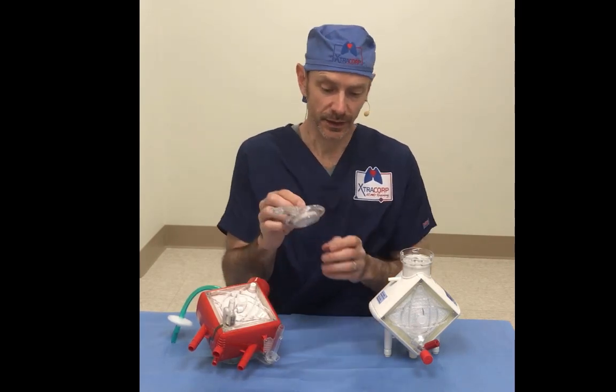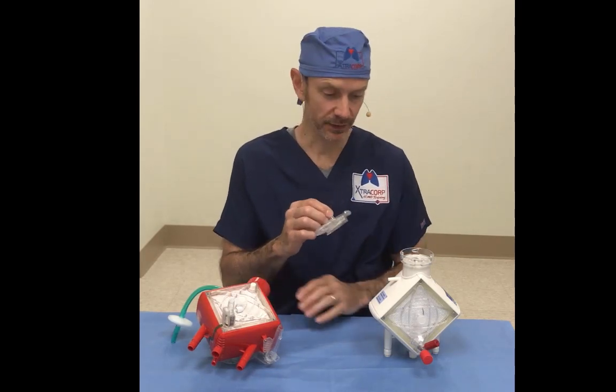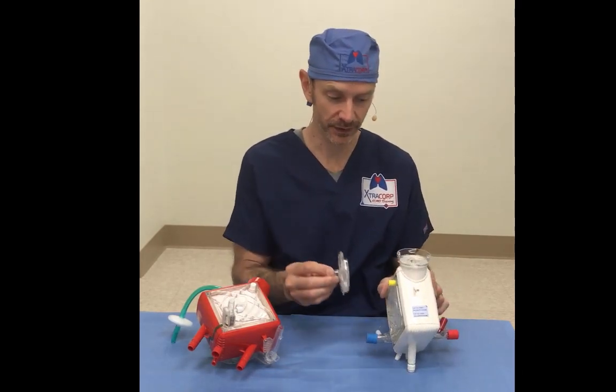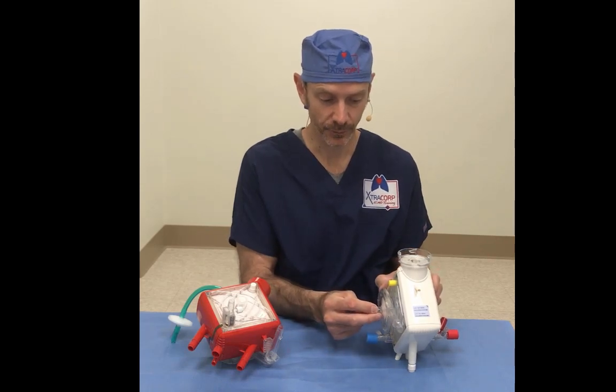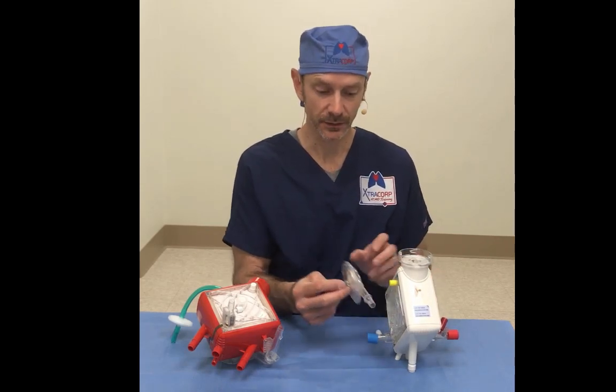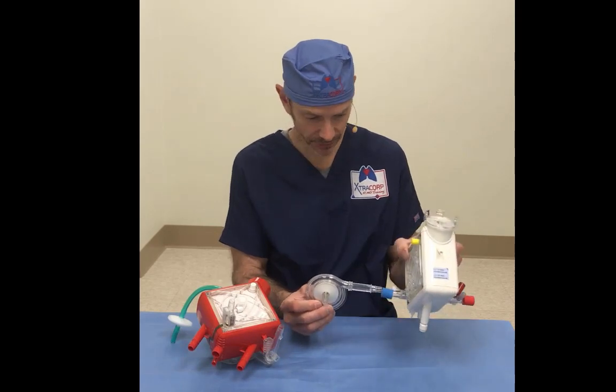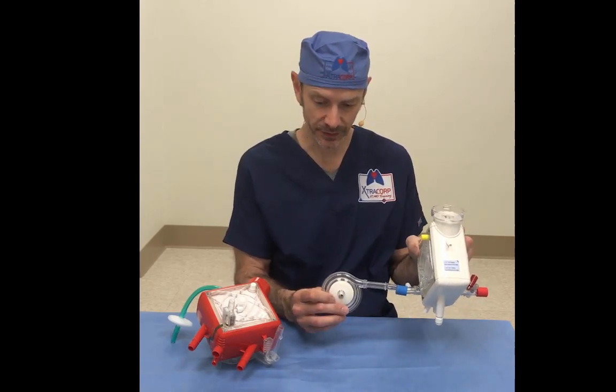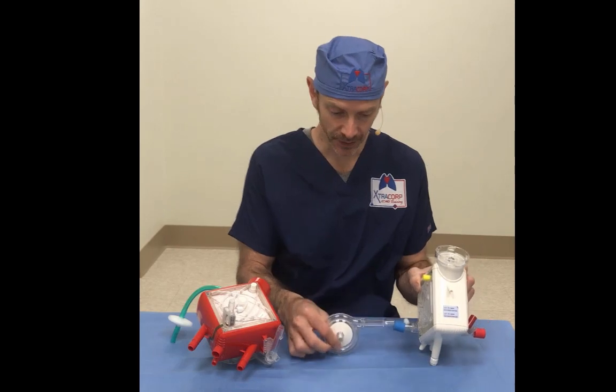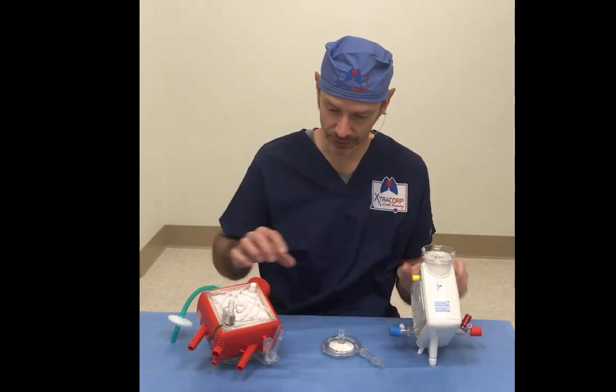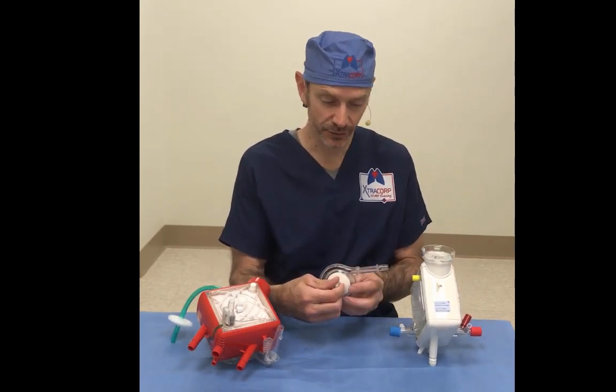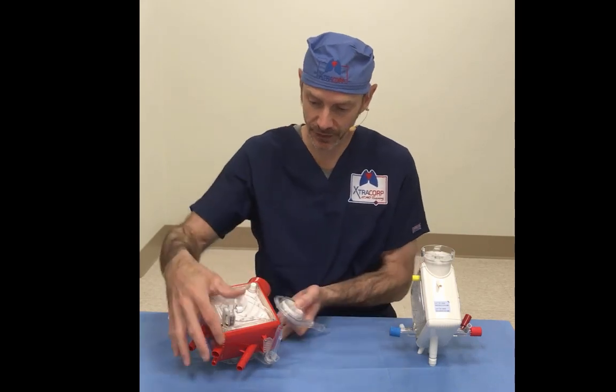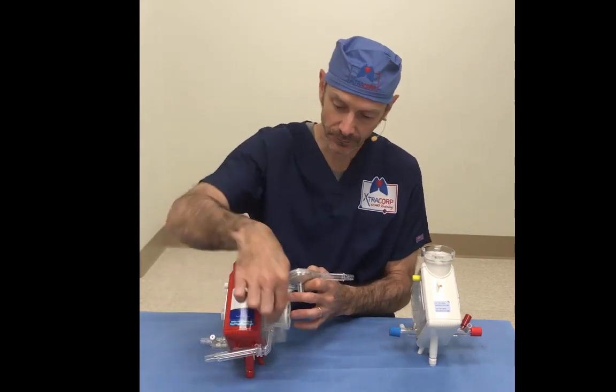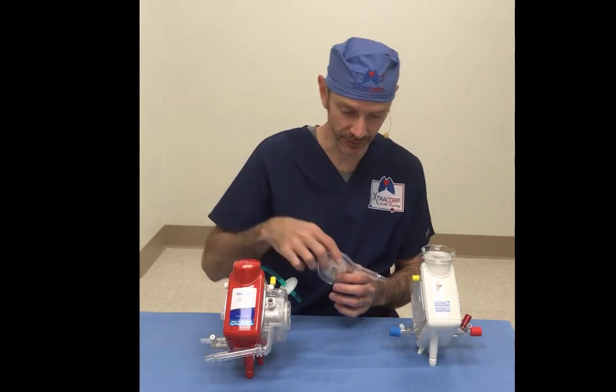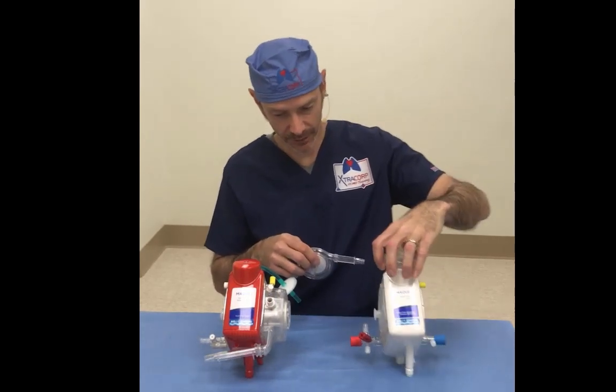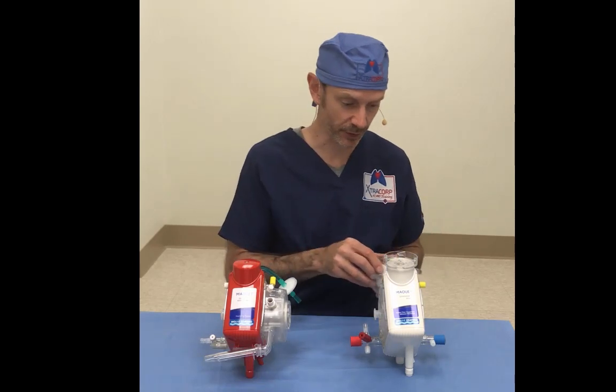And when they made the HLS set, they took a pump and they combined it structurally with an oxygenator. Now, more functionally, it looks something like this, where the inlet of the pump is still a separate connection. That's right here. And the outlet of the pump goes into the oxygenator, but they changed the geometry quite a bit. This pump that's over here, this is the pump on the back of a Quadrox. Now these two oxygenators are in the same orientation.